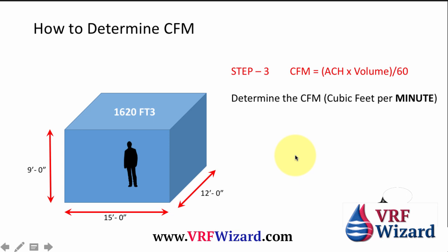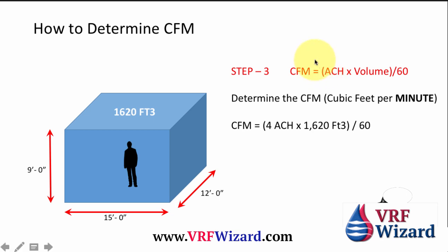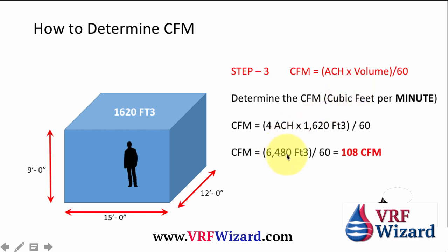Step three: determine the CFM, which is cubic feet per minute. Everything we've done so far has been per hour — air changes in an hour. Now we need to get that down to the minute by dividing by 60. CFM equals air changes times volume, divided by 60. So here we have four times the volume of the room — 6480 cubic feet — divided by 60 minutes in an hour. In this case, that's 108 CFM, which is equivalent to four air changes per hour for this size room.